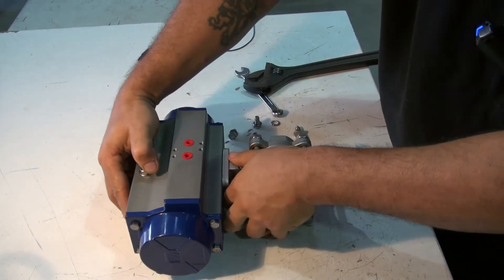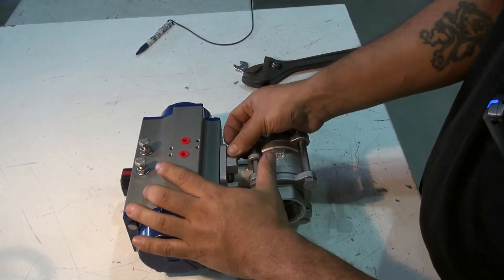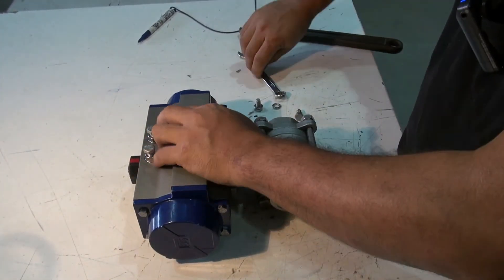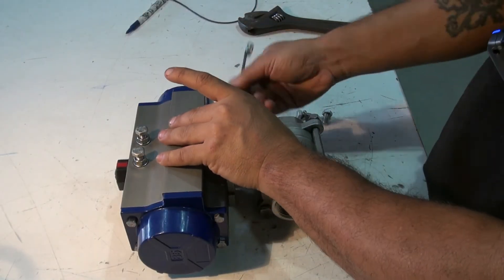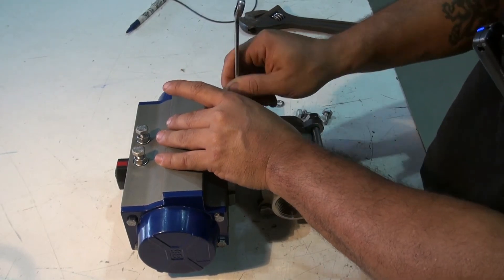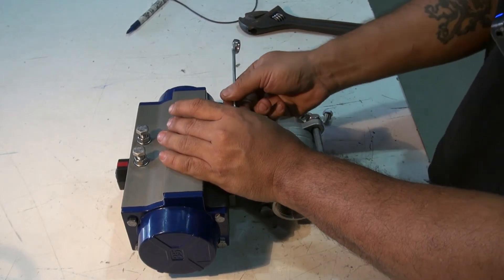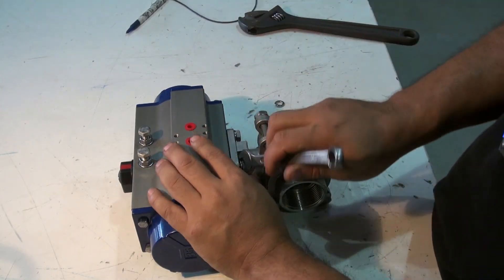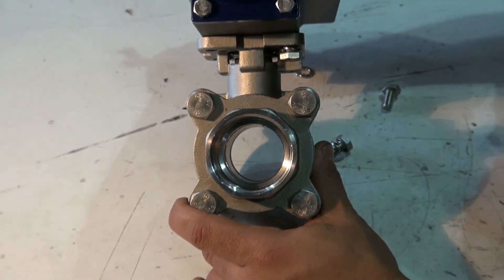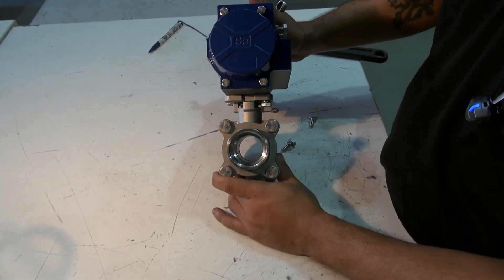Bolt it back up, and I finish bolting it up. The valve should be in the open position. When you actuate it with air, it'll close, and when you disconnect the air, it'll open up again.